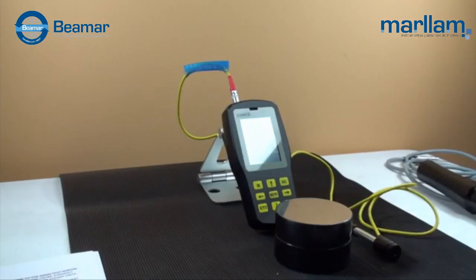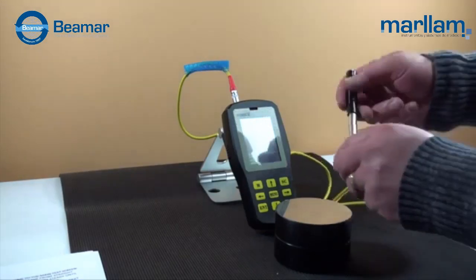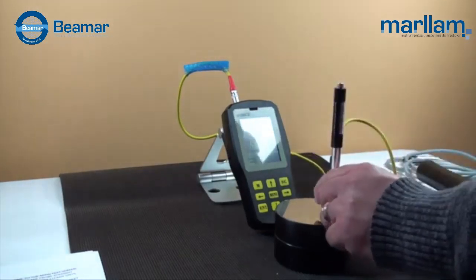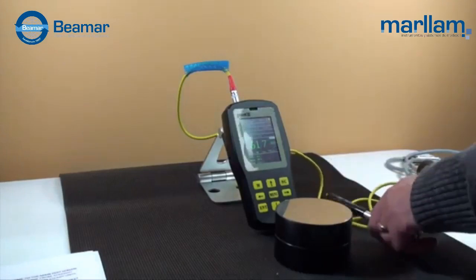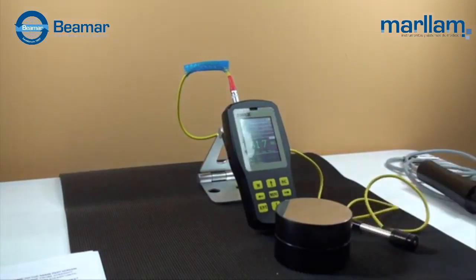For large parts, especially large cast, using the optional Leeb probe is quite simple. Plugging in the Leeb probe, then powering on, you should see the interface show the change to Leeb method, and also the probe type to D or other type of probe that you're using. Taking tests is quick and easy. Spring load the probe and release from the top. The hardness reading will show on the screen. If using a Leeb probe, don't forget to purchase an optional HLD calibration block for verification of accuracy.